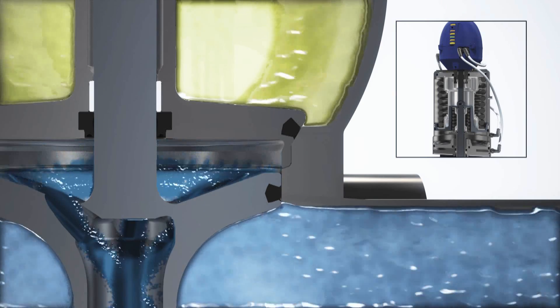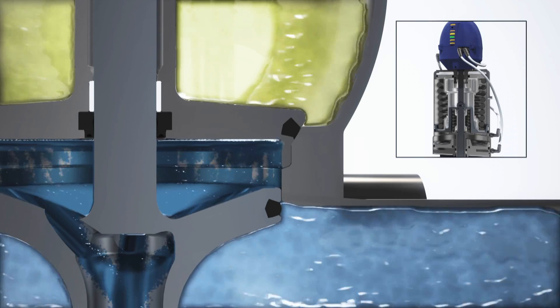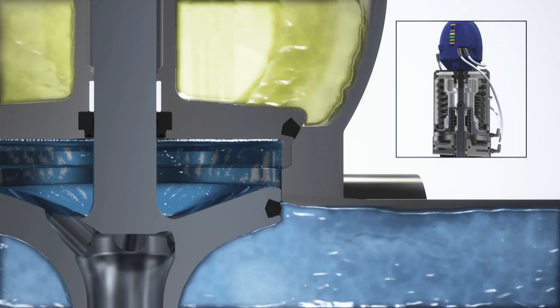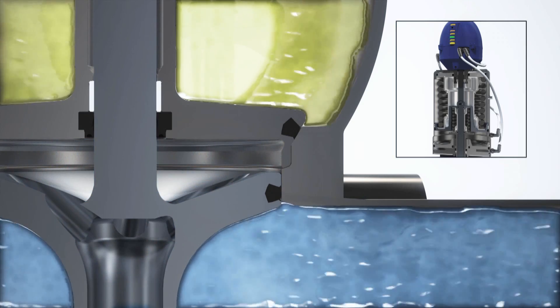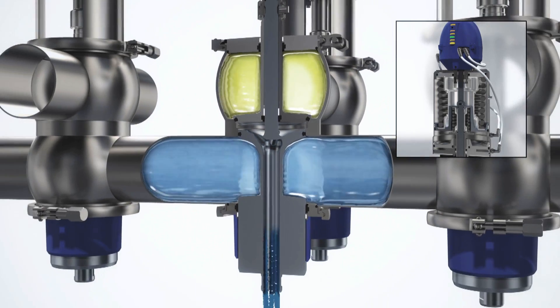This speeds up the cleaning process by creating high turbulence and scrubbing effects, thereby making very efficient use of minimal CIP fluid. It also reduces pressure of the CIP fluid and promotes risk-free cleaning because there is no risk of pressure build-up in the leakage chamber.